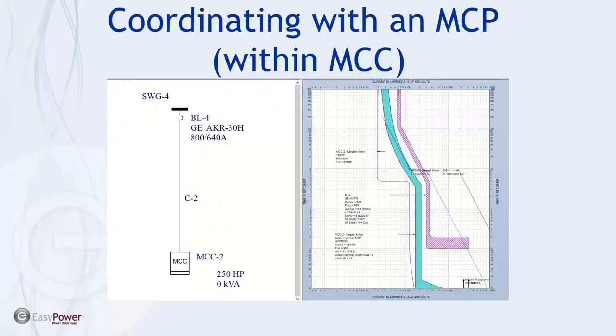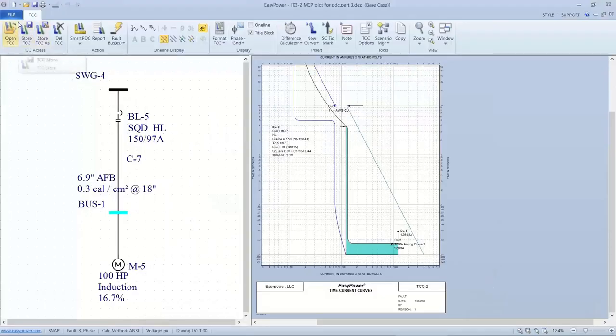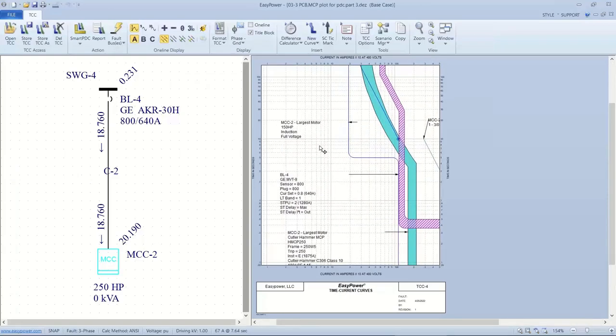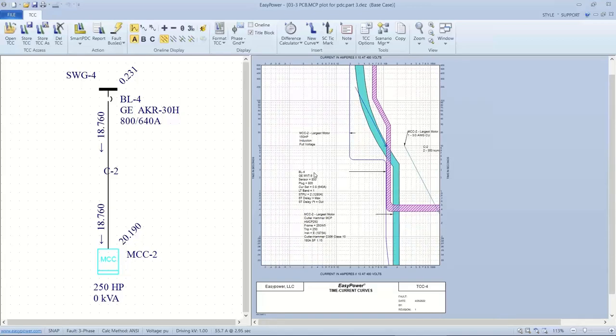Next, I want to emphasize the ability to include an MCP as motor protection as part of a motor control center. In this circuit we have a motor control center fed by a low voltage power circuit breaker. Let me close this and open the relevant one-line. We're feeding a motor control center that has a large 150 HP motor — the largest single load — and we've set up the motor with a TCC to plot the curve.